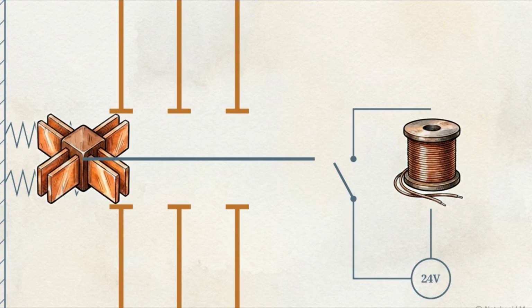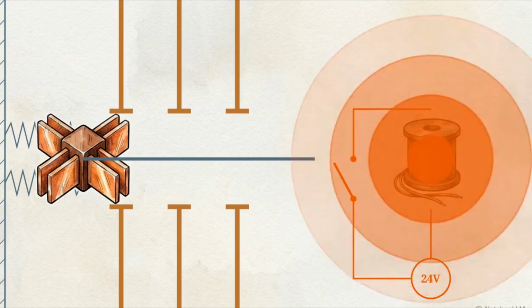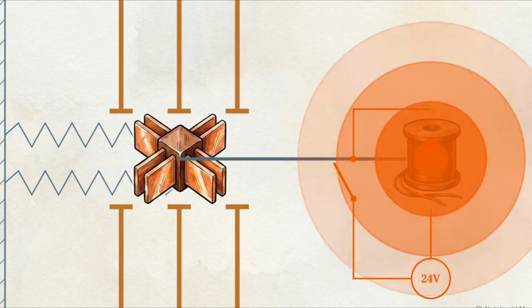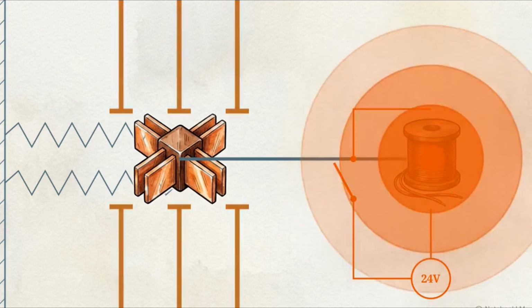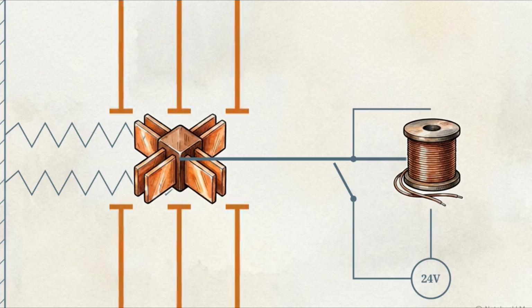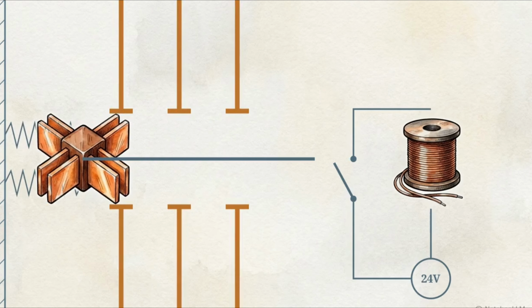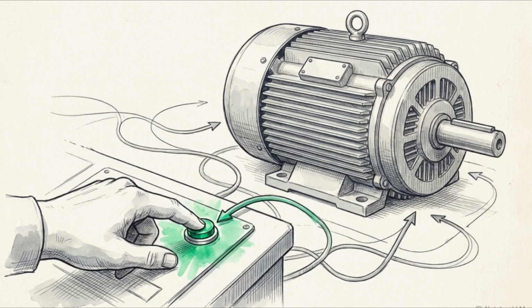There are the three high-voltage contacts, and sitting completely isolated from them is a tightly wound wire coil on a separate 24-volt circuit. When you press a button at a control station, you apply 24 volts to that coil. This causes the energized coil to become a localized electromagnet. That magnetic field pulls the high-voltage contacts closed. The gap is bridged, and the massive three-phase power flows to the motor. When you cut that 24-volt power, the magnetic field collapses instantly. The heavy contacts snap open, severing the motor's power supply. This achieves electromechanical isolation. We can safely manipulate lethal high voltage from a distance, using nothing more than the magnetic field of a low-voltage coil.